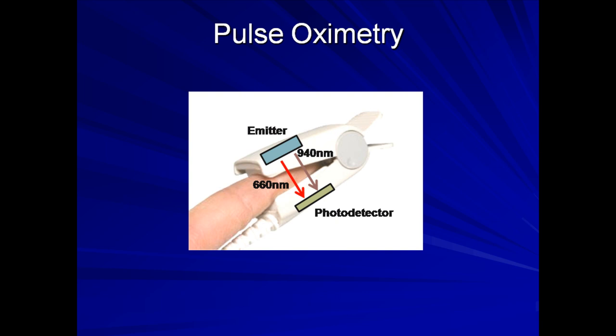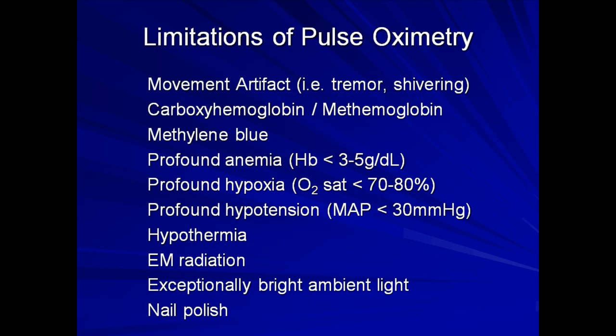The photo detectors only register transmitted light of alternating intensity — otherwise the pulse oximeter would erroneously report values based on light transmission through veins and extravascular tissue. Pulse oximetry has a long list of potential limitations, though most are rare causes of false readings. They include movement artifact, dyshemoglobinemias, methylene blue, profound anemia, profound hypoxia, profound hypotension, hypothermia, ambient electromagnetic radiation, exceptionally bright ambient light such as in an operating room, and certain shades of nail polish.